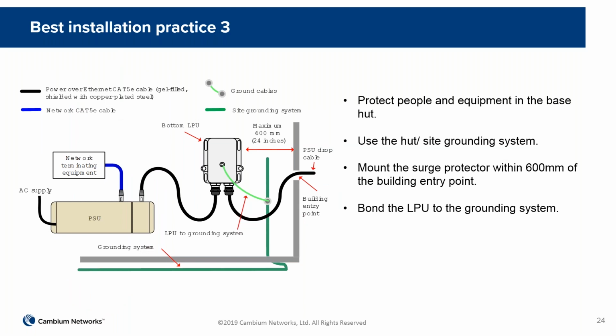And then in detail at the equipment hut, as I mentioned, we have something of the order of a maximum of 2 feet between the bottom LPU and the building entry point. We have a grounding system within the hut, and we connect that LPU to that grounding system. So we can come in on a well shielded and screened cable.